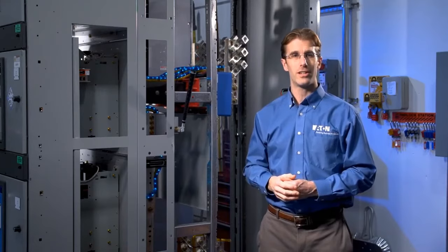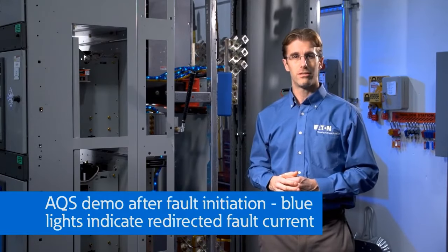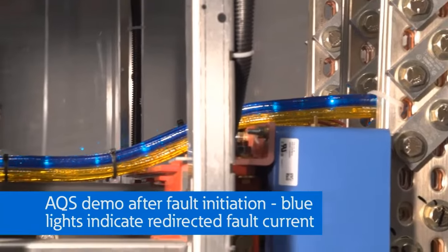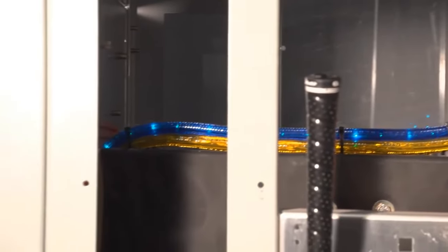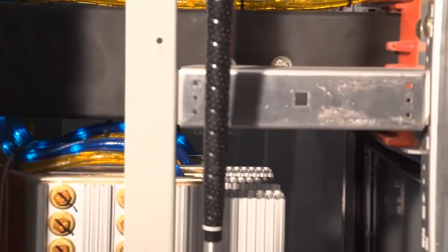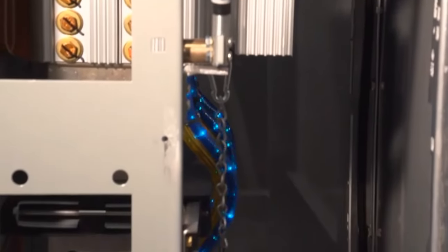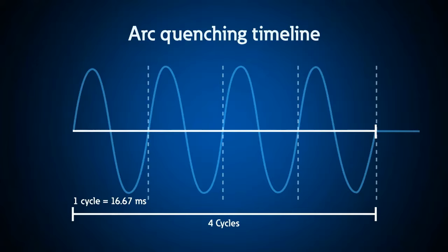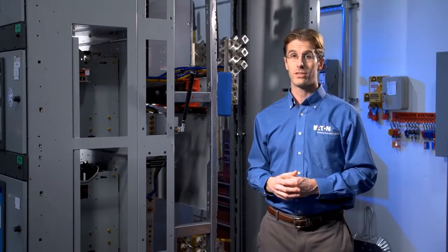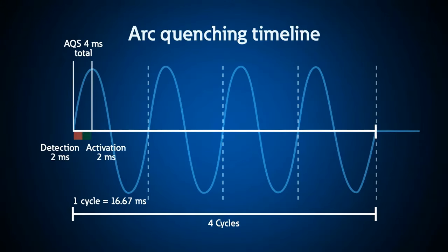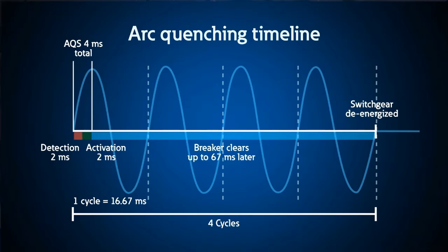Oh, big arc flash. Now you'll notice the blue chasing rope lights have illuminated. All of the current is now flowing into the blue arc quenching device. It's no longer flowing through the wrench, which initiated that arcing fault. So the arcing fault instantly extinguishes because all of the current flows into the arc quenching device. That actually occurs in a total of 4 milliseconds. That's less than a quarter of a cycle. It takes about 2 milliseconds to detect the arc flash, which is done by the Eaton arc flash relay and those arc flash sensors that I pointed out, and another approximately 2 milliseconds to commutate that arc energy and contain it inside the arc quenching device until the main breaker opens up and de-energizes the lineup about 3 to 4 cycles later.